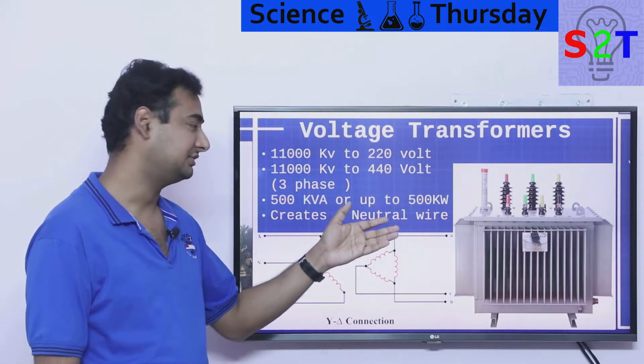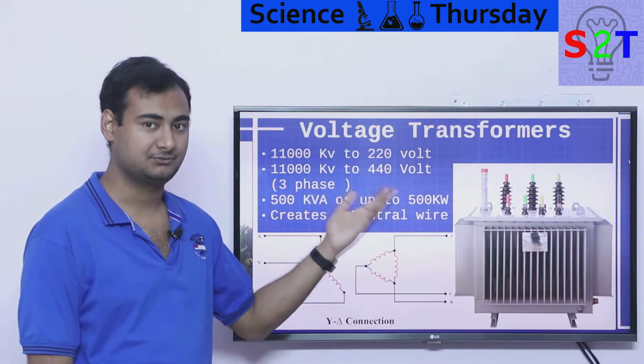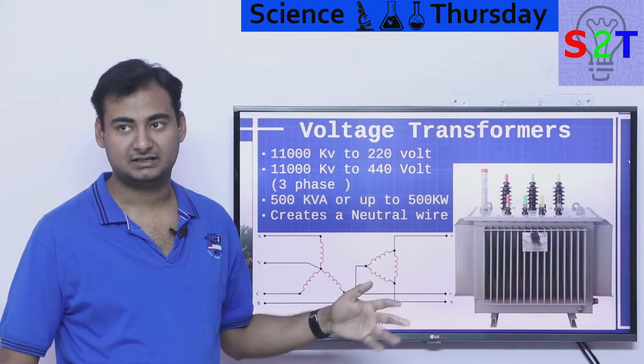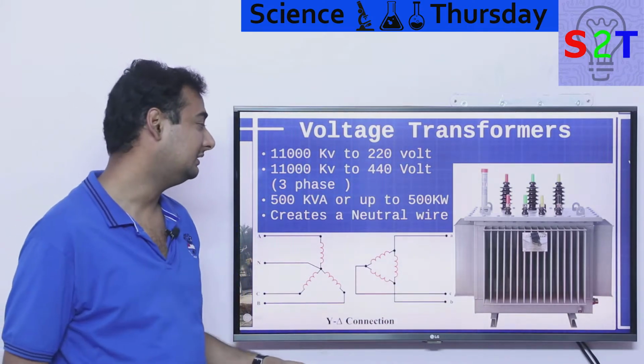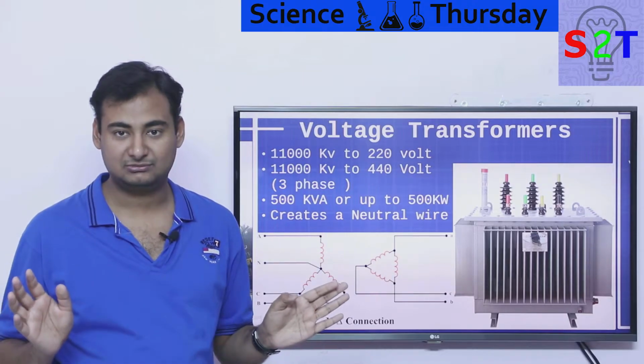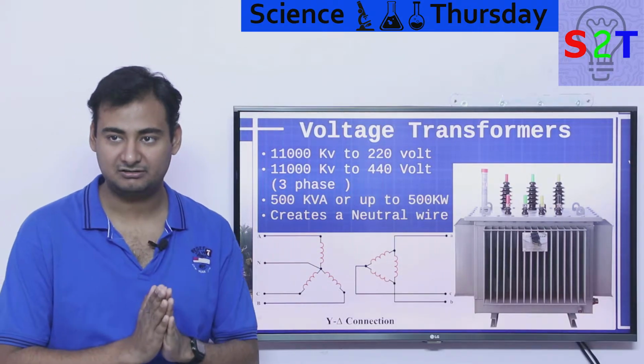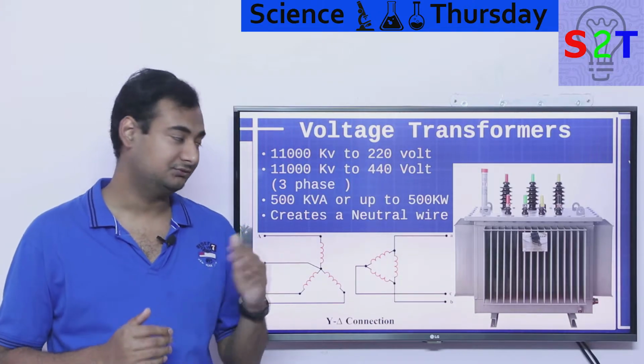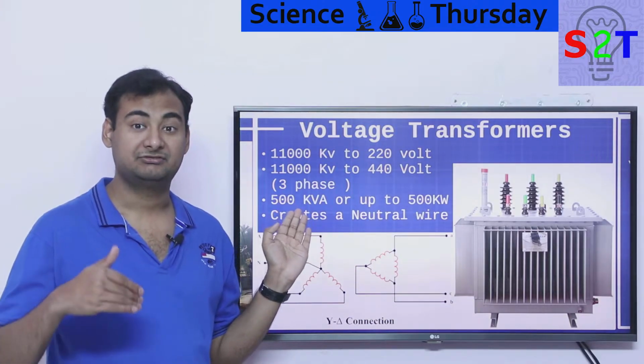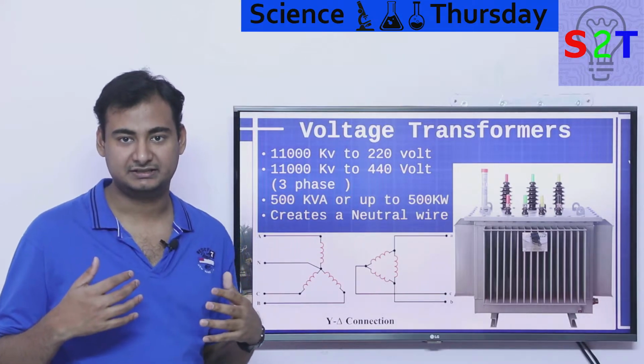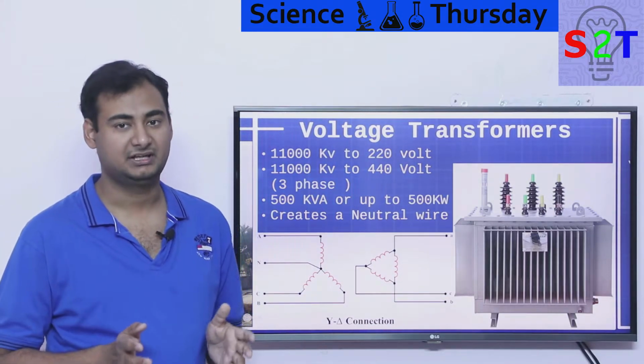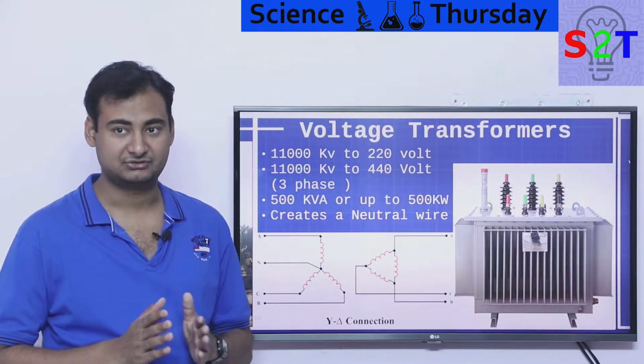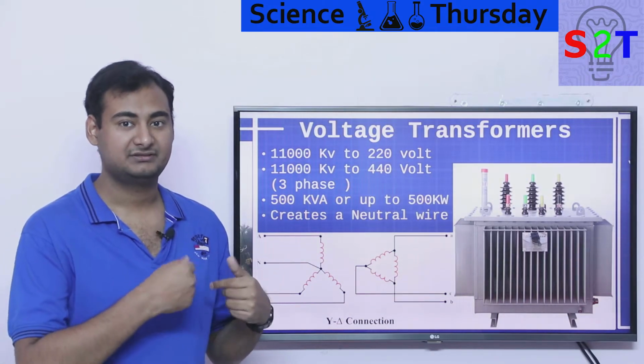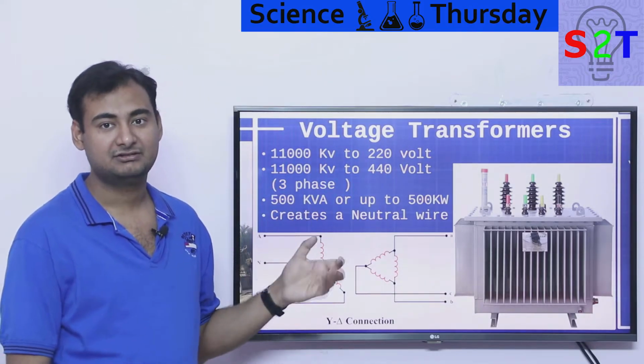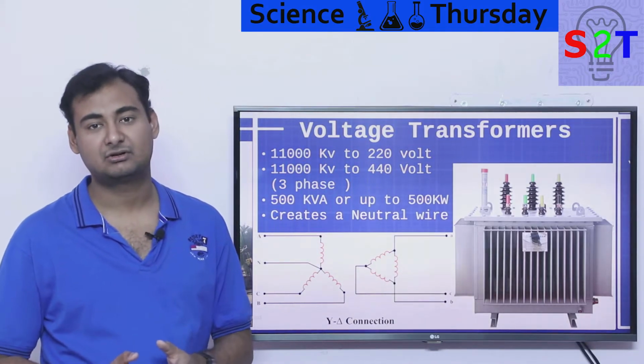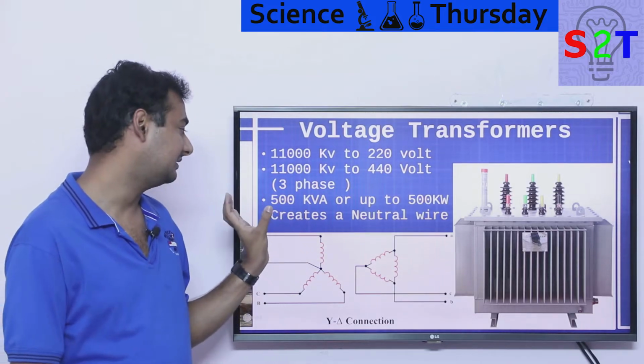Now you might be wondering why we don't simply say 500 kilowatt. It's a transformer, it's supposed to provide power. Why don't we say power that we understand? Oh, my motor is 10 kilowatt, my motor is all that. The reason is power factor. That's a completely complicated subject, don't worry too much about it. Basically, if you have a good power factor, closer to 1, awesome, you can draw upwards of 500 kilowatt. But if your power factor is bad, which generally it is, let's say you are running a computer with a bridge rectifier in the power supply, that messes up the power factor, so it becomes like 0.7, and that 0.7 gets multiplied. For that reason, you can never draw as much current as you want. Your practical current draw would be limited. That's why a transformer is always rated in kVA.